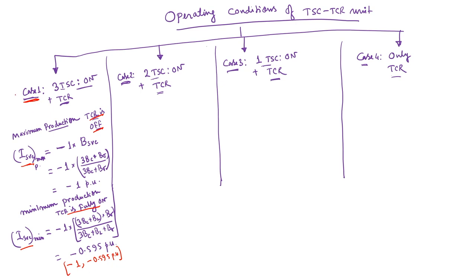So it can be operated at partial conduction mode as well. So these two values of ISVC max and ISVC min, for this particular case, correspond to two extreme possible operations of this TCR: one is fully off, another is fully on. So that means when TCR is partially on, it can produce VAR starting from the range -1 to -0.595 per unit. Any value of this VAR within this range is possible by using TCR control in case A. So that is something one needs to understand.